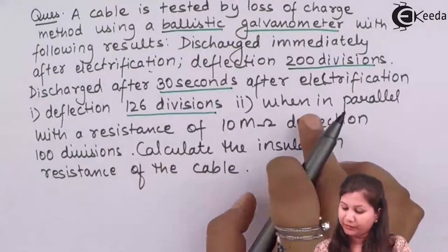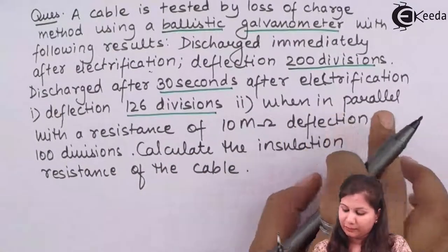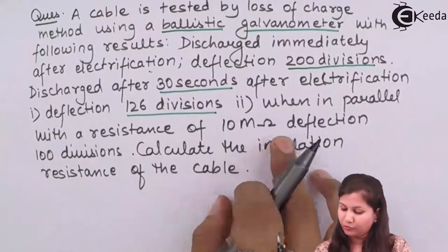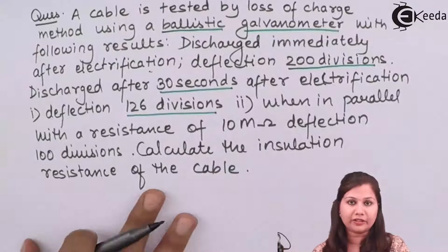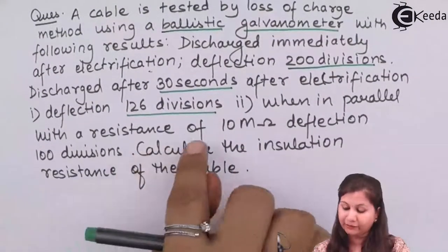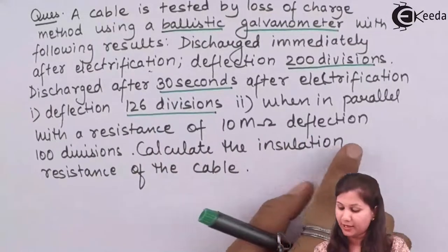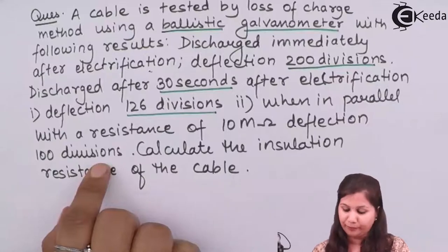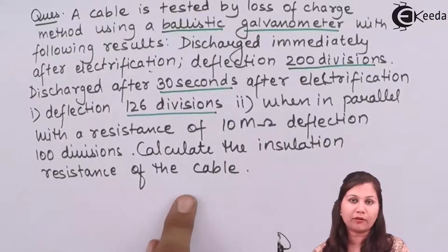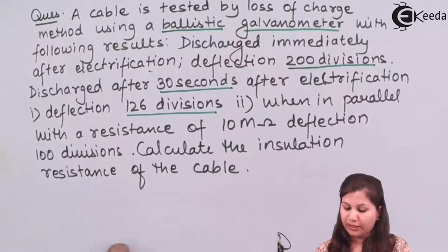When the unknown insulation resistance is in parallel with a resistance of 10 mega ohm, the deflection on the galvanometer is 100 divisions. Using all this information, we have to calculate the insulation resistance of the cable.